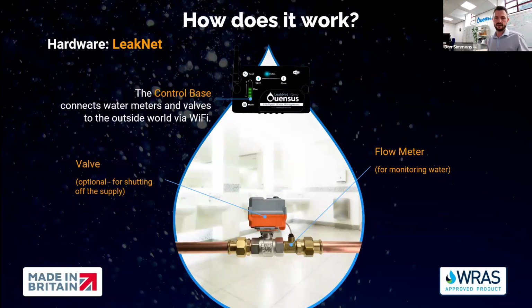The hardware is fairly simple. It's a flow meter, a standard water meter, but the ones we use are very high resolution. Water meters generally used for billing have low resolution but are very accurate, which is what water companies want. For leak detection, you need slightly different technology that gives high resolution - less accurate, but it means you'll get notifications within a minute if there's a problem, rather than after a month.